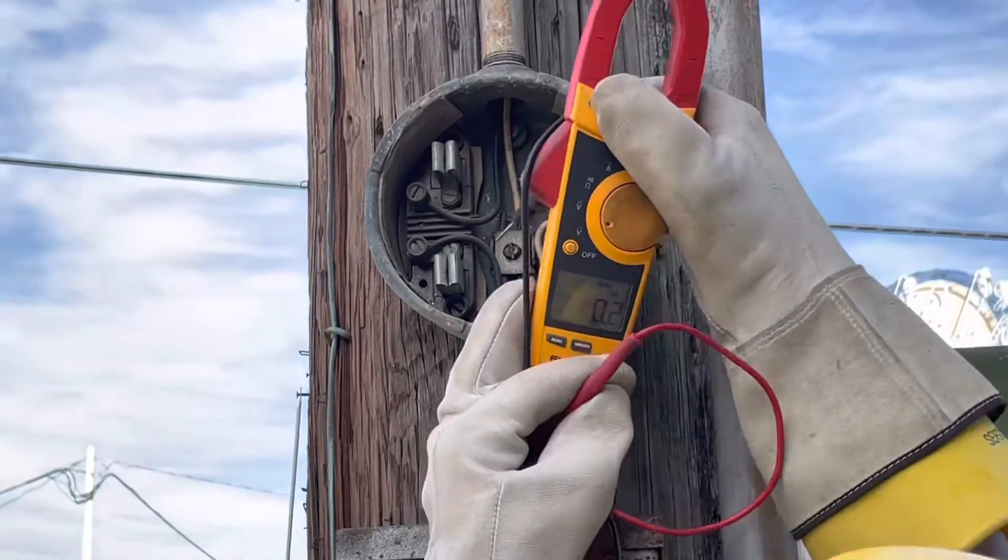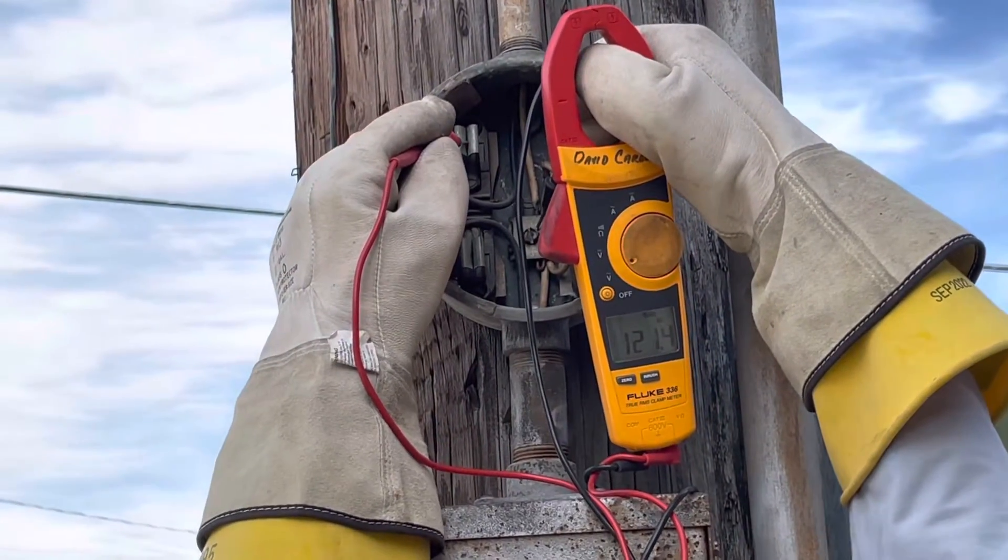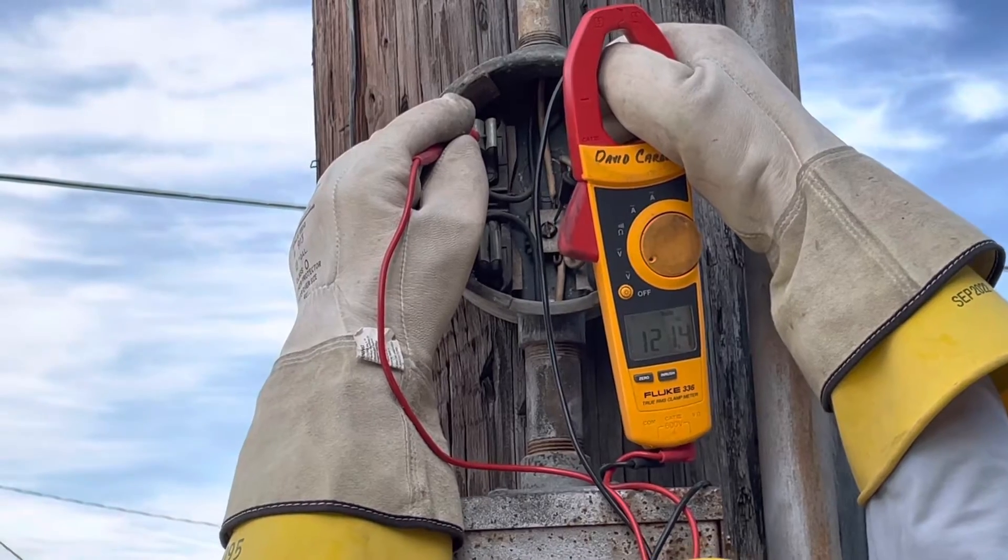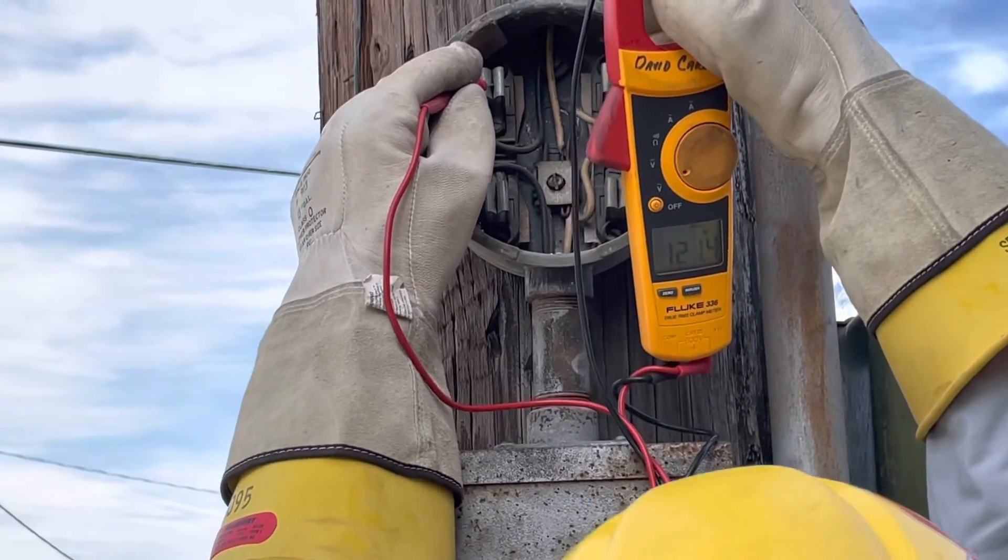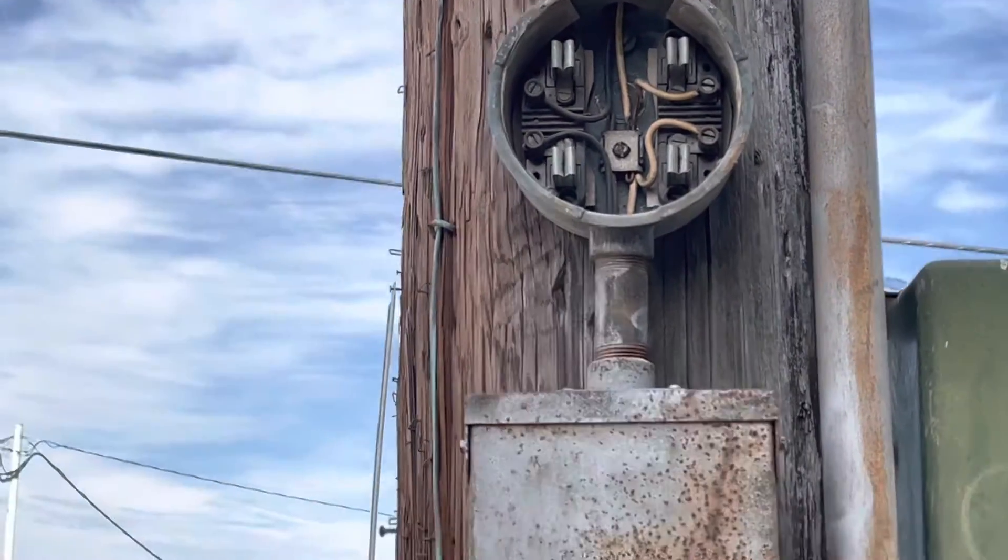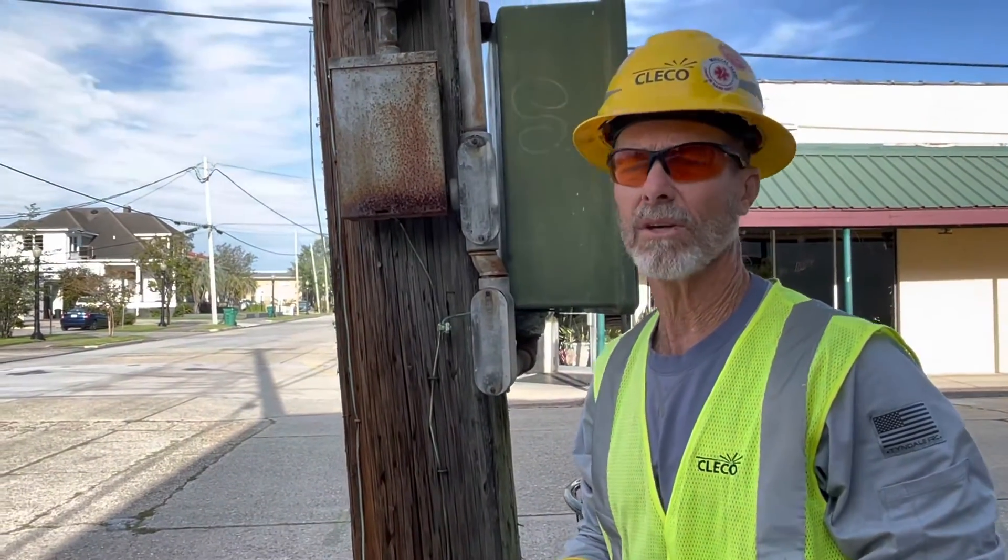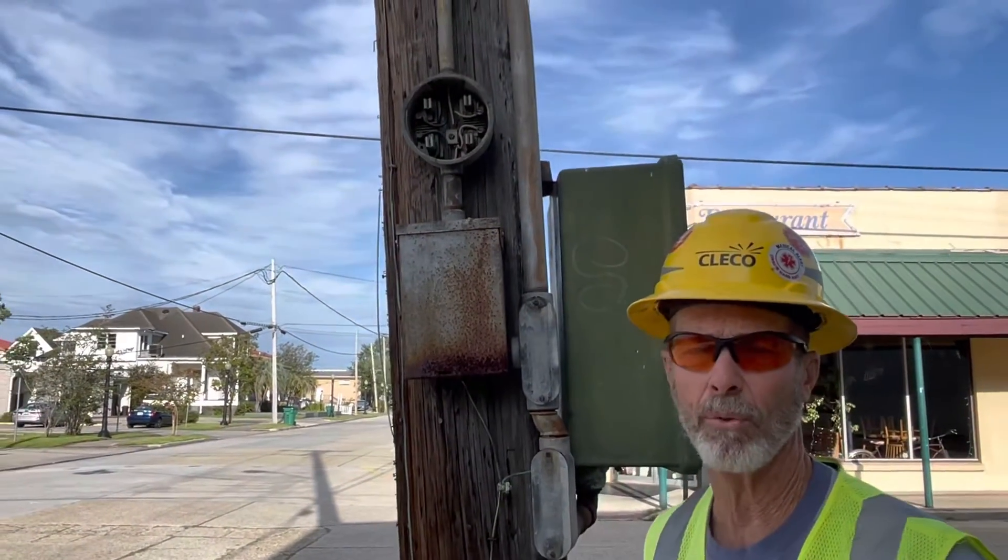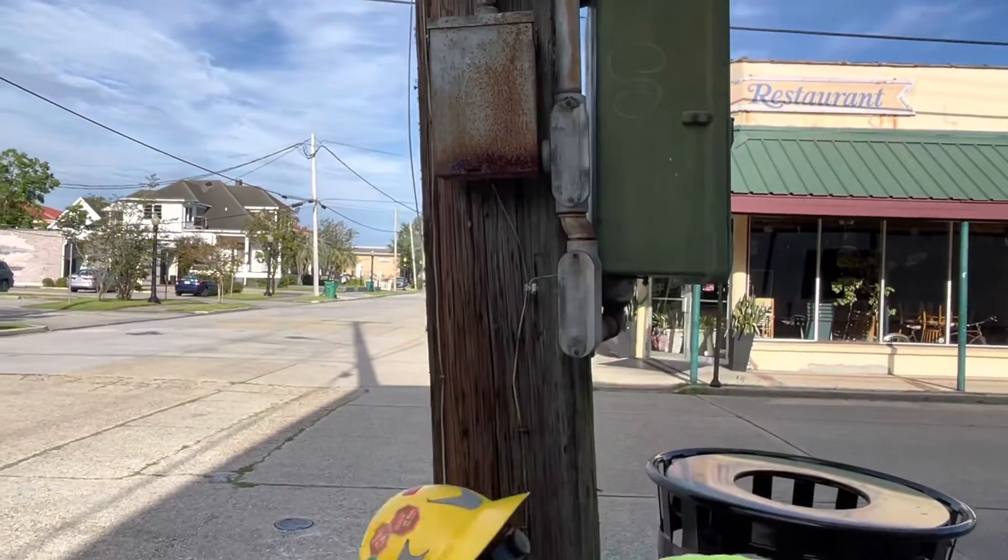Let me see if I can see my volt meter. 120 volts phase to ground, that is the ground, and I'm going to have 120 volts to the neutral. So that tells me this is a single phase two wire service and I need to put a form 1S meter in it. Here's the proper way to put it in.